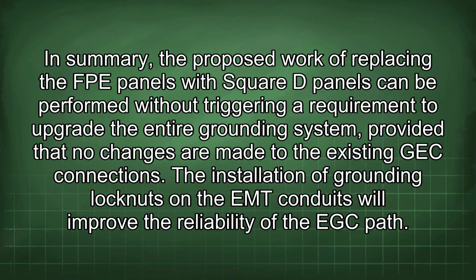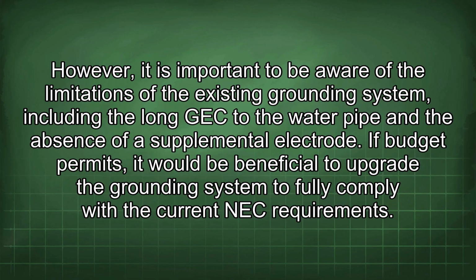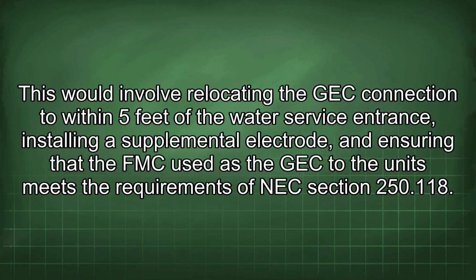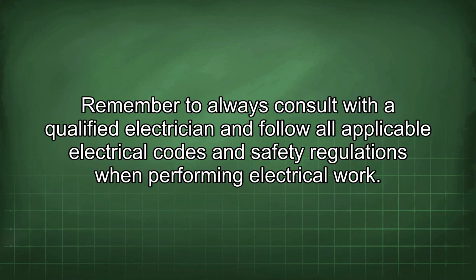without triggering a requirement to upgrade the entire grounding system, provided that no changes are made to the existing GEC connections. The installation of grounding lock nuts on the EMT conduits will improve the reliability of the EGC path. However, it is important to be aware of the limitations of the existing grounding system, including the long GEC to the water pipe and the absence of a supplemental electrode. If budget permits, it would be beneficial to upgrade the grounding system to fully comply with the current NEC requirements. This would involve relocating the GEC connection to within 5 feet of the water service entrance, installing a supplemental electrode, and ensuring that the FMC used as the EGC to the units meets the requirements of NEC Section 250.118. Remember to always consult with a qualified electrician and follow all applicable electrical codes and safety regulations when performing electrical work.